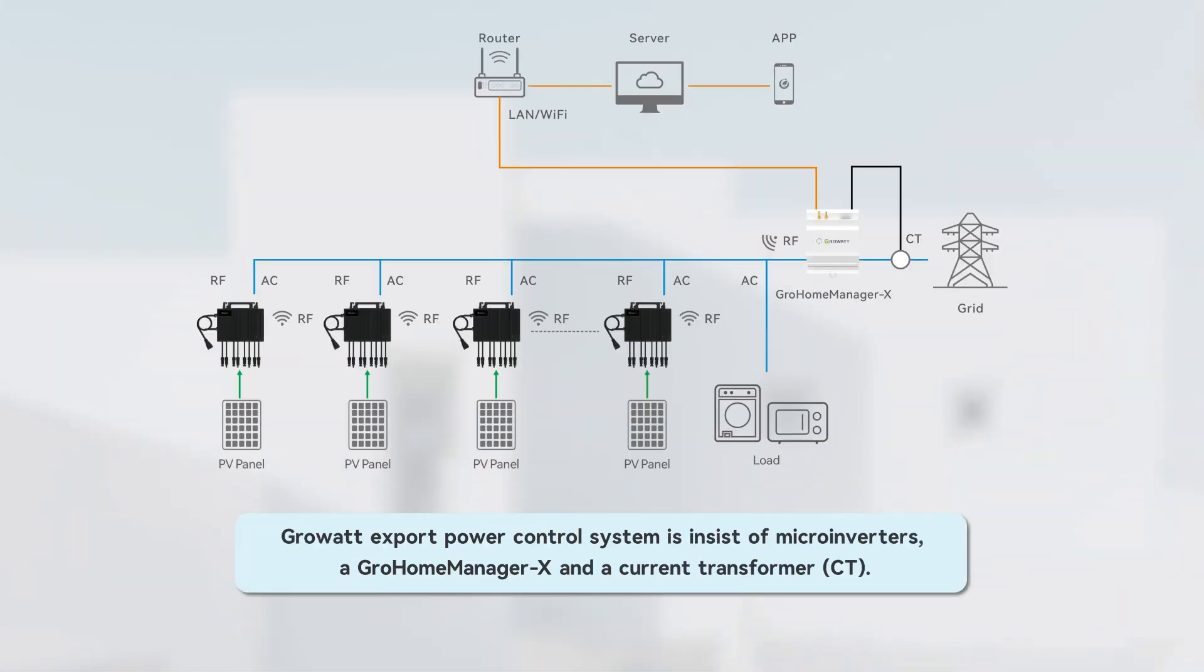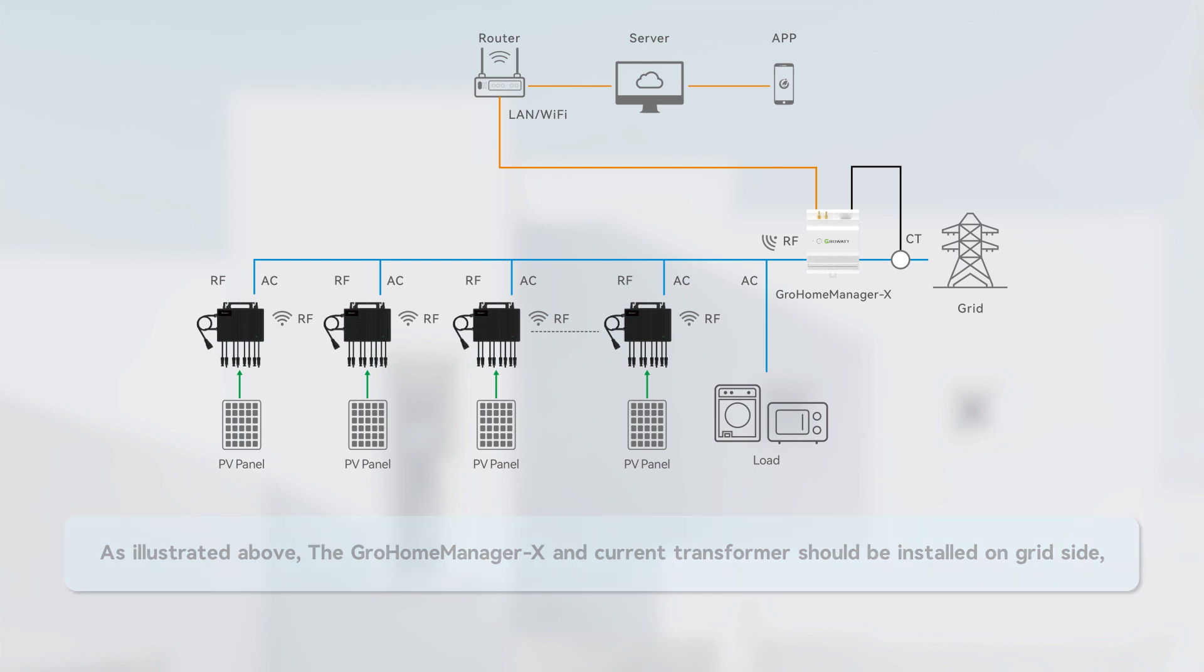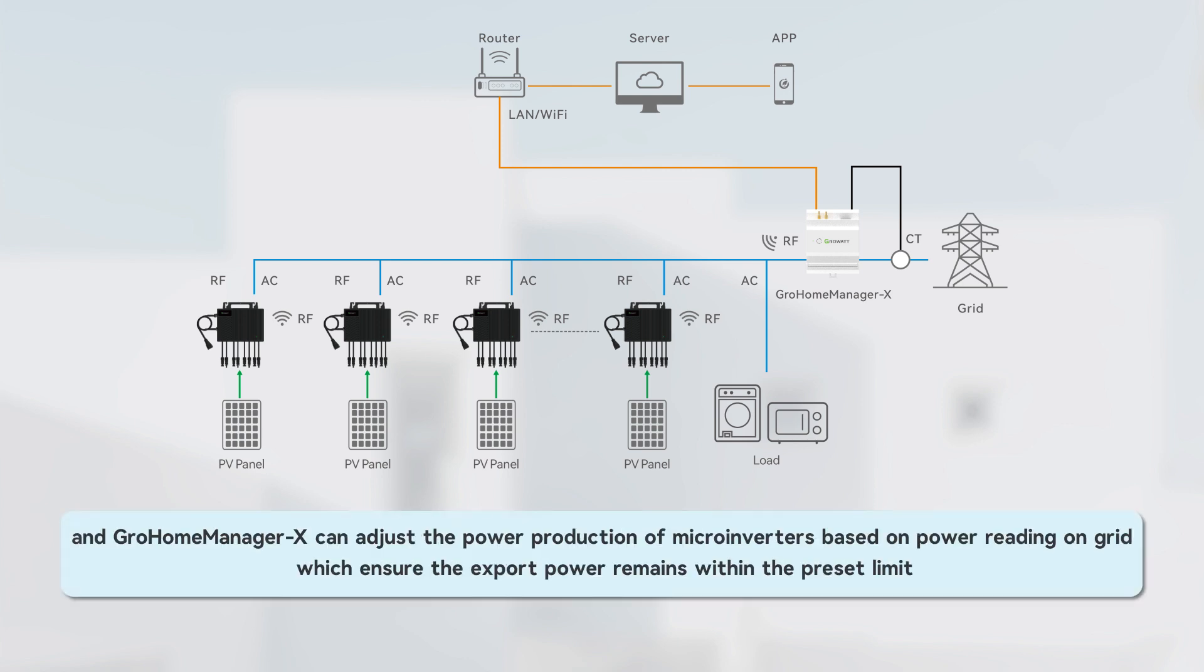Growatt export power control system consists of microinverters, a GroHomeManager-X, and current transformer. As illustrated above, the GroHomeManager-X and current transformer should be installed on grid-side, and GroHomeManager-X can adjust the power production of microinverters based on power reading on grid, which ensures the export power remains within the preset limit.